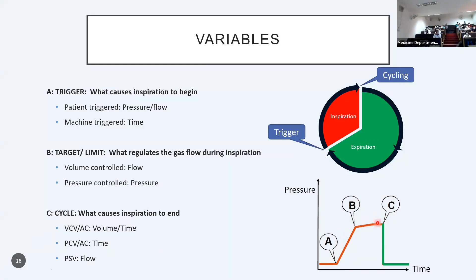So as I talked, there are two broad modes of ventilation: pressure controlled ventilation and volume controlled ventilation. Pressure controlled, as the name implies, is where the clinician controls the pressure or sets a pressure to be delivered to each breath. For example, we can see in this PCV mode, the pressure in each breath is constant, though the volume may change. In the volume control mode, the volume is constant. For example, with each breath, the volume and the flow is constant, though the pressures may change.